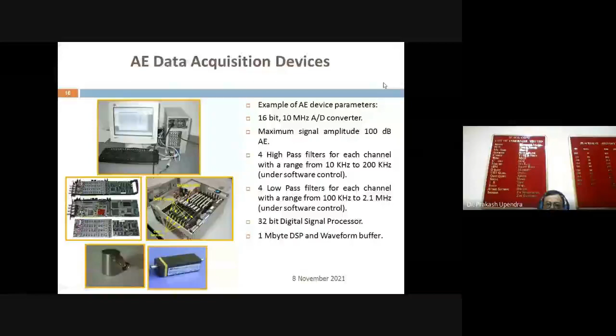Now the principles of AE data measurement and analysis: threshold and hit definition time. Threshold and HDT are parameters used for the detection of AE signals. HDT enables the system to determine the end of the hit, that is, from the beginning to the end of the hit. It is referred to as the HDT. So it closes out the measuring process and stores the measured attributes of the signals. There will be hit 1 or hit 2, and based on the distance, it will be referred to as long HDT and short HDT.